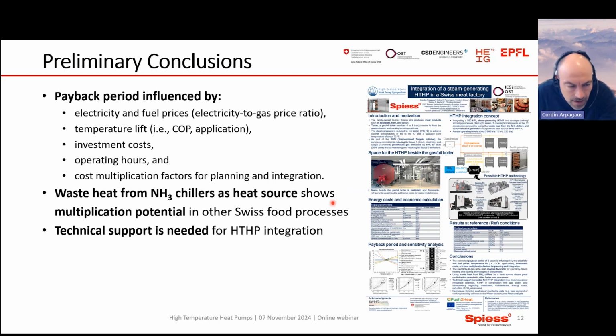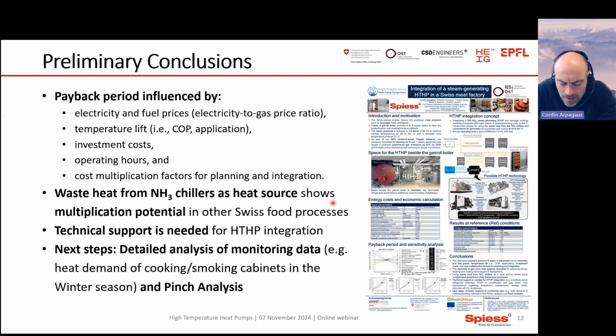But we also recognize there is a need for technical support for the integration, because this is not available at the company. At this company with 160 employees, there are one or two persons that would deal with such energy questions and possible integration of a new heat pump. So they need external support. The next step was then to have real data, so monitoring data and pinch analysis. This is a case where the production just started with this new building, with this new production site, and the gas boiler was installed and running, so the first months of this gas boiler could be monitored to see really the steam demand.